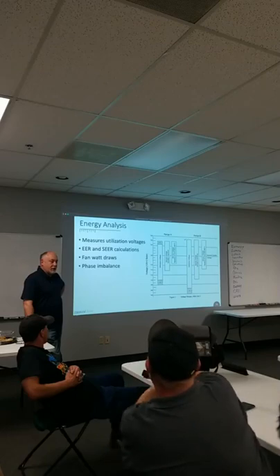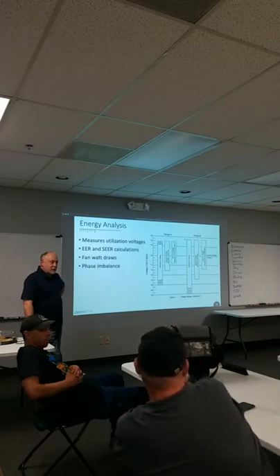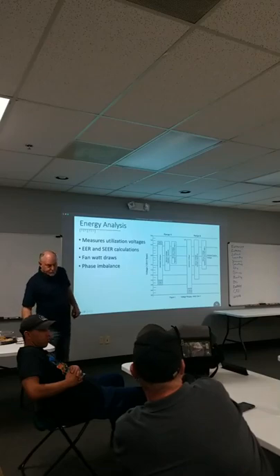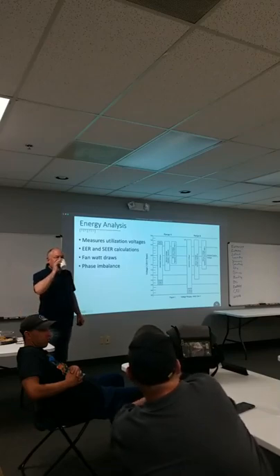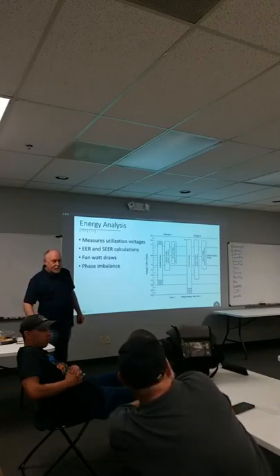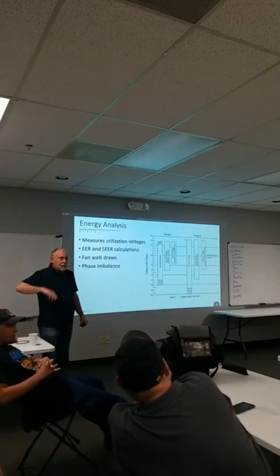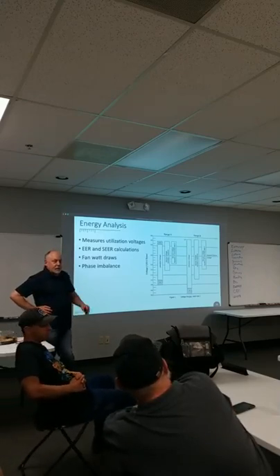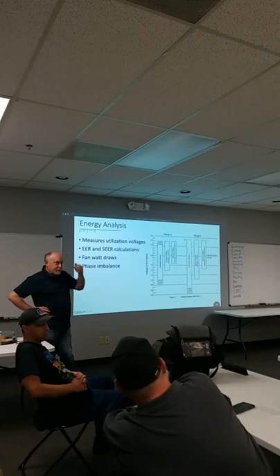If your load voltage continues to go up, your amps will go up also, because you've got a fixed load and a higher voltage, so you're pushing more amps through that motor. There's a range where they're designed to run. If volts go down too much, amps go up, but if volts are too high, they'll go up also.